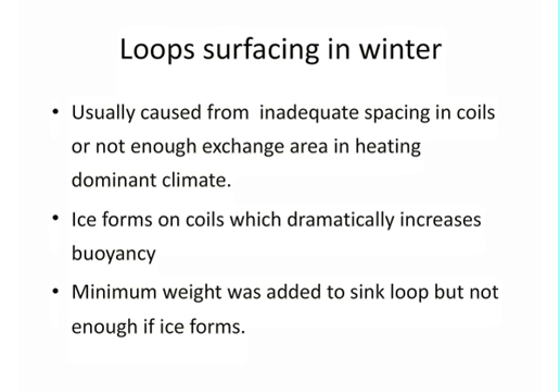Well, what happens in your heating dominant climate is you start to drop that temperature, since you don't have all that 300 foot or whatever happened to be a coil as a surface area in contact with the water so the water can flow. You start to build ice. And when you start to build ice, that adds buoyancy. And typically you don't have anywhere near enough weight. And most of these guys put just enough weight to make the pond loops disappear when they install them. So what happens? Well, the pond loop comes back up, and now, Houston, you have a problem because your pond loop is at the surface.